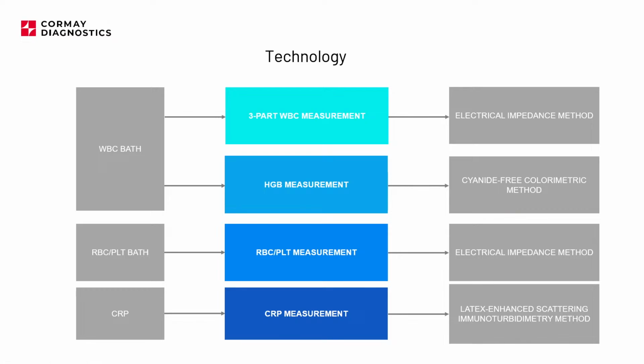So we are checking our background. So background will be clear diluent in the chamber, and later after this reaction, I mean, we destroy the red blood cells, and hemoglobin is already combined into some compounds. We are checking what is the difference of the absorbance at this point, and basically the difference in absorbance is proportional to the concentration of the hemoglobin according to the device calibration.